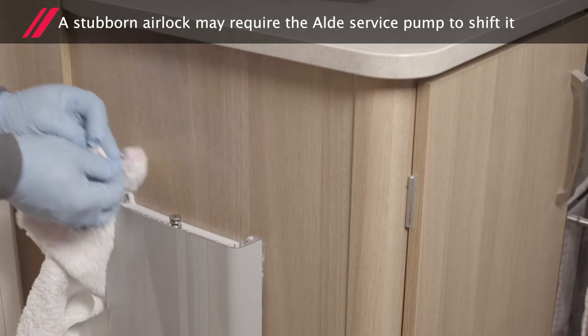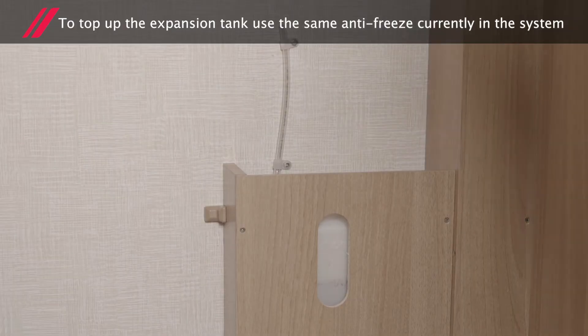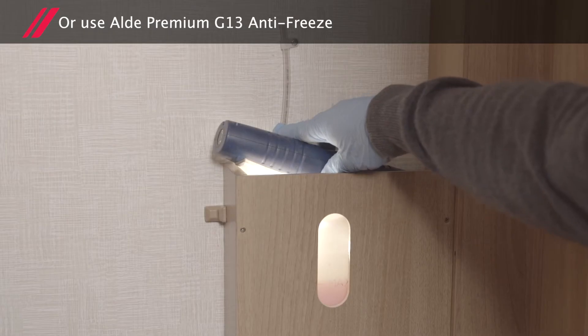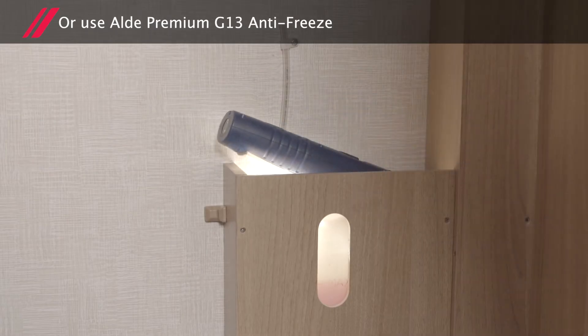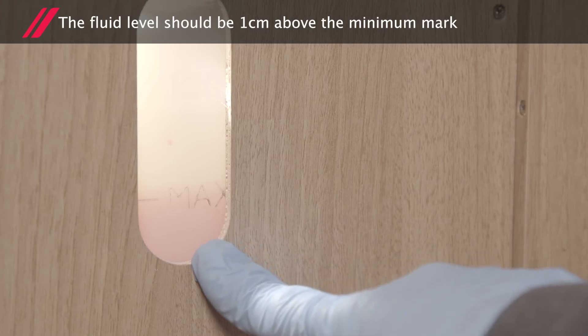A stubborn airlock may require the Alde service pump to shift it. To top up the expansion tank, use the same antifreeze currently in the system, or you can use the Alde Premium G13 antifreeze. The fluid level should be one centimetre above the minimum mark.